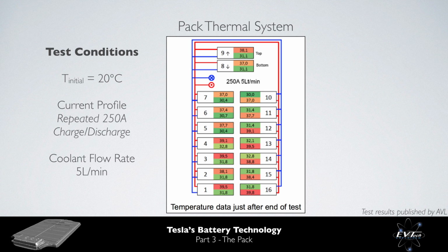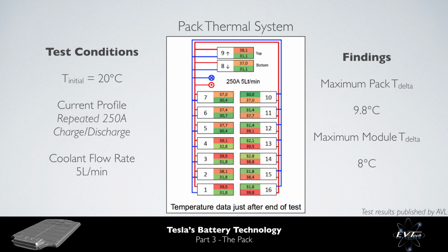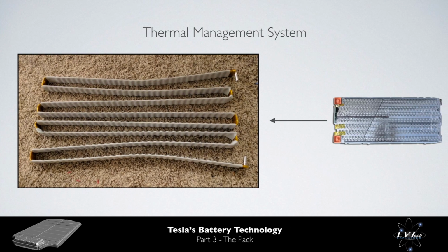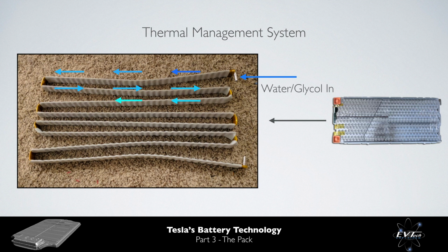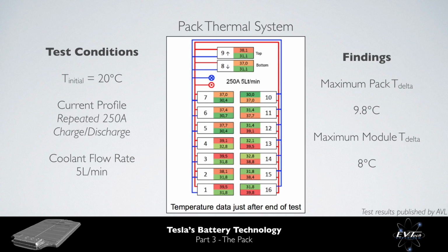Each module contains 2 temperature sensors, which enable measurement of a cell temperature near the module cooling inlet and a measurement of the cell temperature near the module cooling outlet. It is desirable to minimize cell-to-cell temperature variation, as hotter cells will be worked harder and degrade faster. It is seen that under these test conditions, pretty significant temperature differences arise, with almost a 10-degree temperature difference across the pack and an almost 8-degree temperature difference over some modules. The large temperature differences between the cells near the inlet and the outlet of the module arise as the coolant runs through the module in a series fashion. Hence, it is hotter towards the outlet than towards the inlet. The cooling system does, however, seem to do a good job at preventing cell temperatures from becoming excessively high.